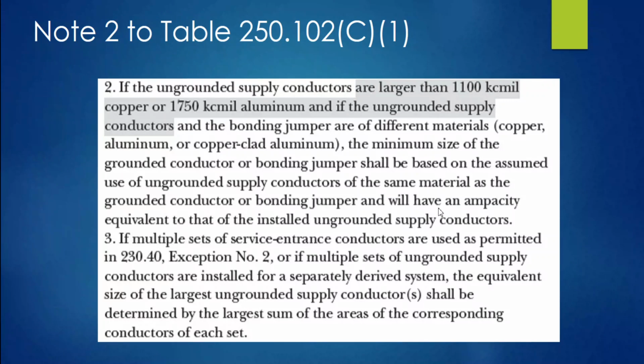Okay, so basically what it's saying is, let's make sure we cover it. If I'm using a bonding jumper and the material of that bonding jumper is different than what I used for the ungrounded supply conductors, then I'm going to actually size that main bonding jumper as if it was the same material as the ungrounded supply conductors. Okay. All right.